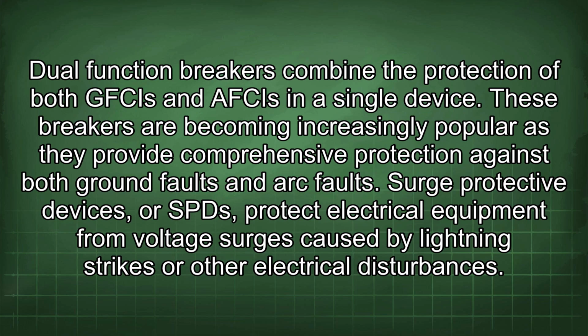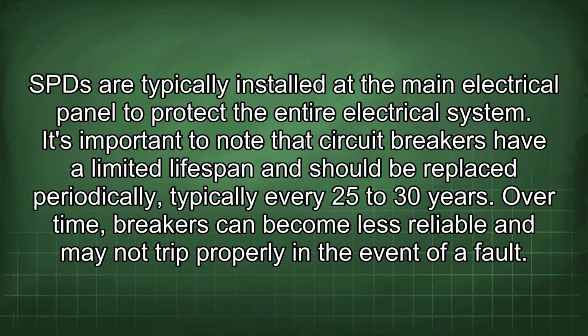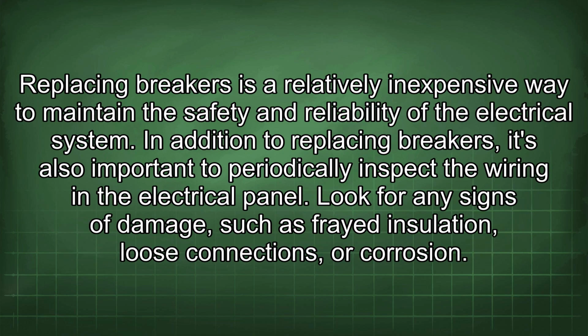Surge protective devices, or SPDs, protect electrical equipment from voltage surges caused by lightning strikes or other electrical disturbances. SPDs are typically installed at the main electrical panel to protect the entire electrical system. It's important to note that circuit breakers have a limited lifespan and should be replaced periodically, typically every 25 to 30 years. Over time, breakers can become less reliable and may not trip properly in the event of a fault. Replacing breakers is a relatively inexpensive way to maintain the safety and reliability of the electrical system.